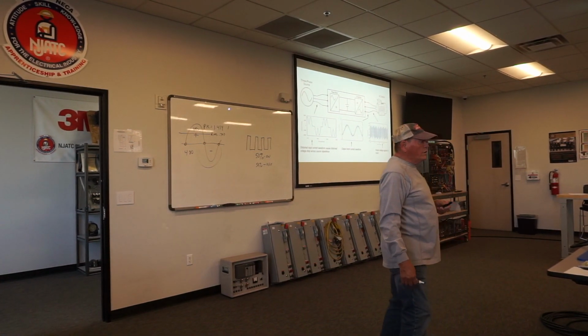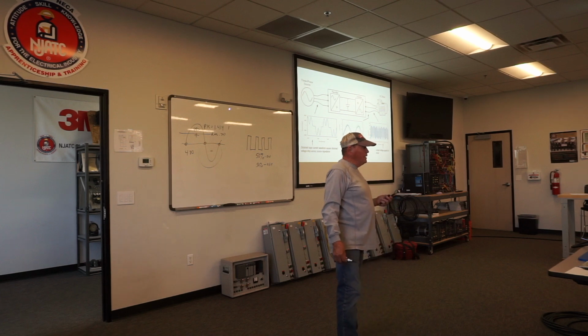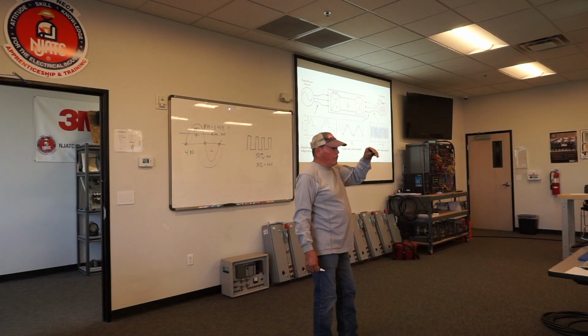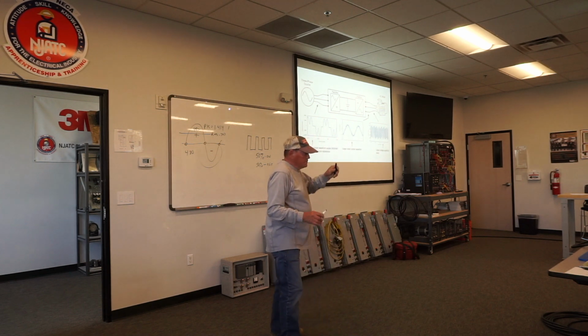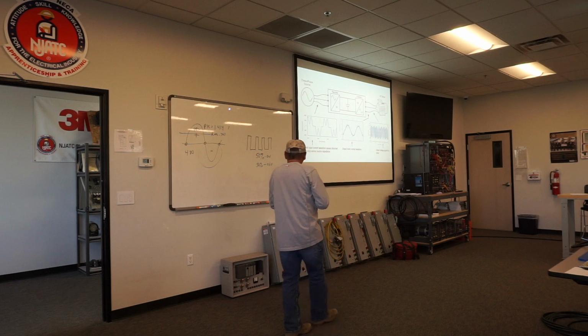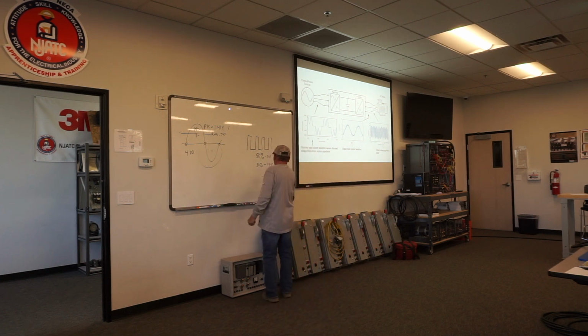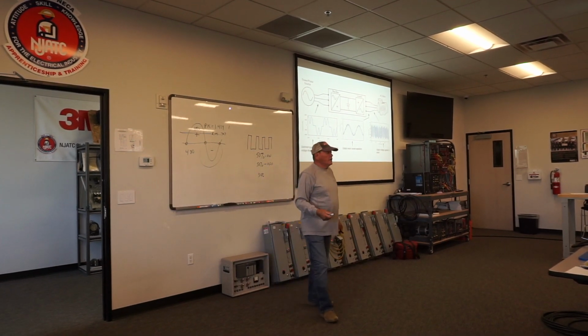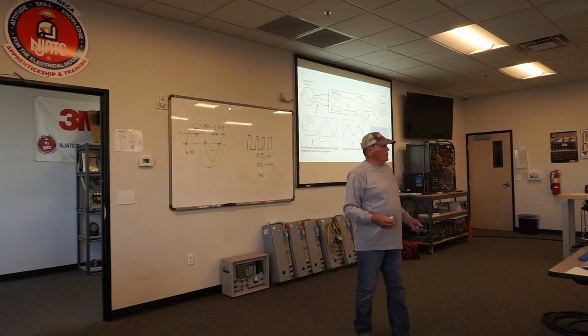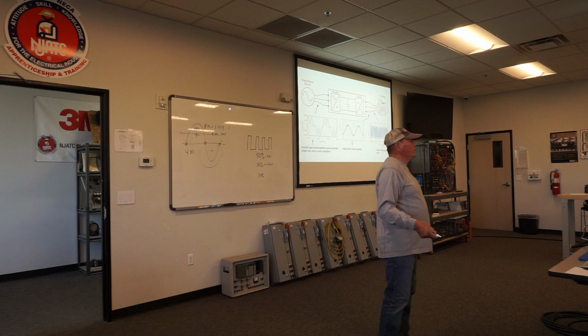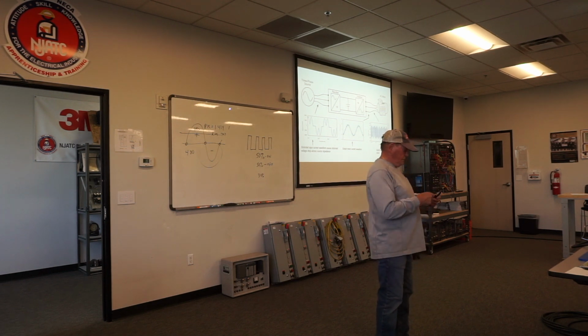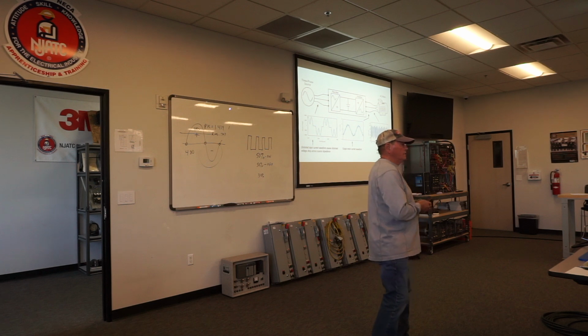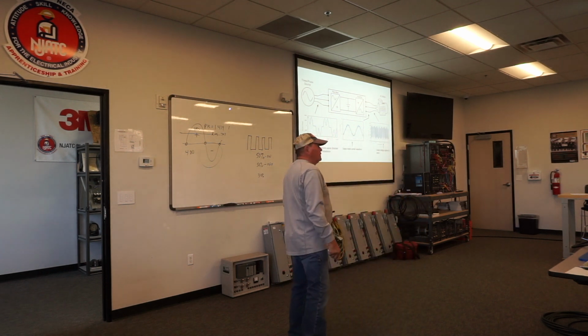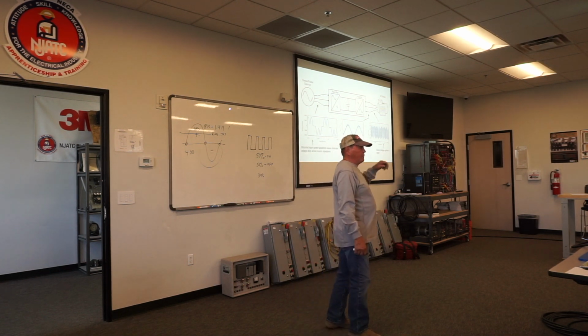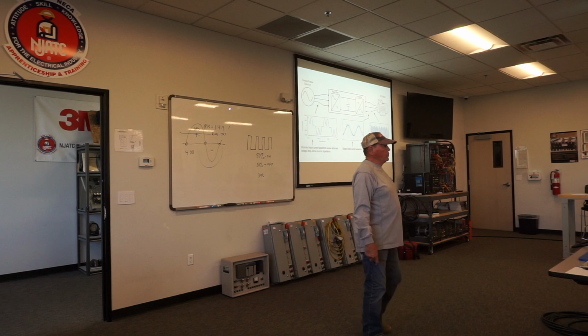Now I can overspeed a motor, maybe around 5% overspeed, meaning I can run it a little higher than 60 hertz, but it depends on the motor. And how slow can I spin a motor? Depending on the motor, maybe 30%. Because a motor needs cooling. Where does the cooling come from? The fan built inside the motor. So if I don't spin that motor fast enough, the motor can overheat. So there's limits to how low I can spin a motor, and there's limits to how high I can spin a motor, and a VFD can do both. Spin too high, spin too low.